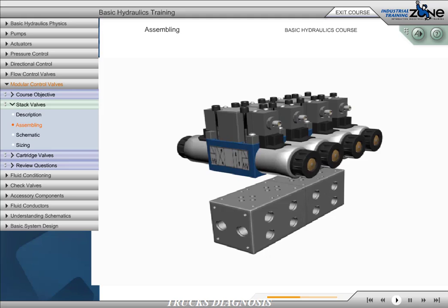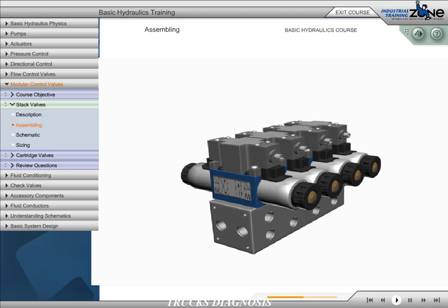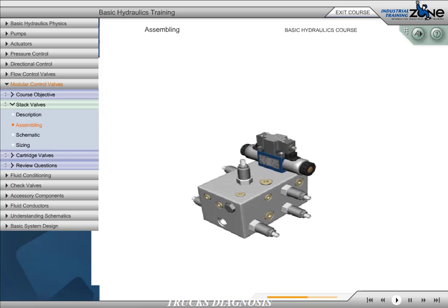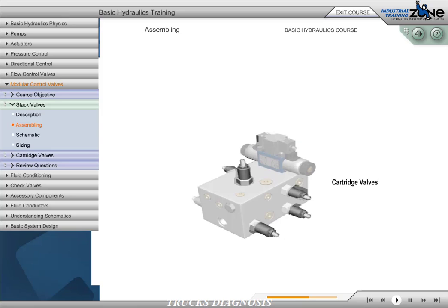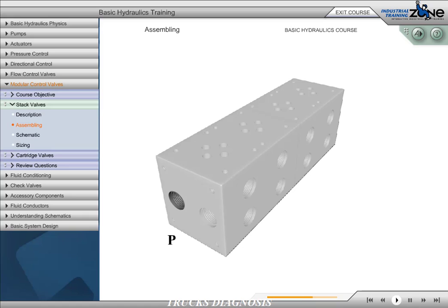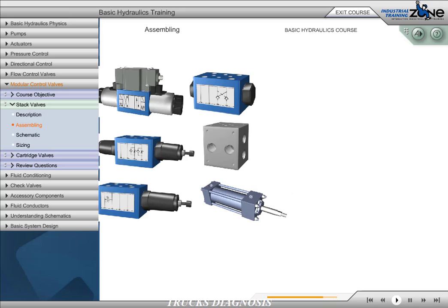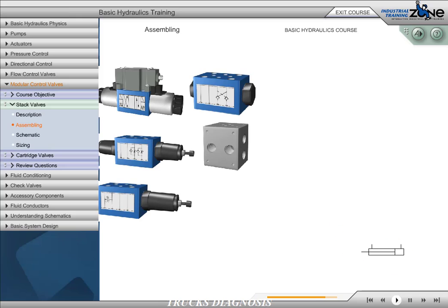A single valve stack can be mounted on a manifold block or subplate, while multiple valve stacks can only be mounted on a manifold block. Each valve stack would be used to control an actuator. Stack valves can be mounted on a manifold block in conjunction with circuits containing cartridge valves. Subplates and manifolds have a supply P port, a return T port, and A and B work ports, which line up with corresponding P, T, A, and B ports on the mounting surface. Manifolds and subplates with X and Y ports can be supplied when using directional control valves that require an external pilot or external drain. Watch as the following components are converted to a schematic of a single stack that controls an actuator.